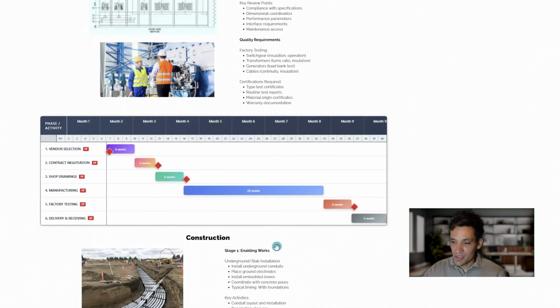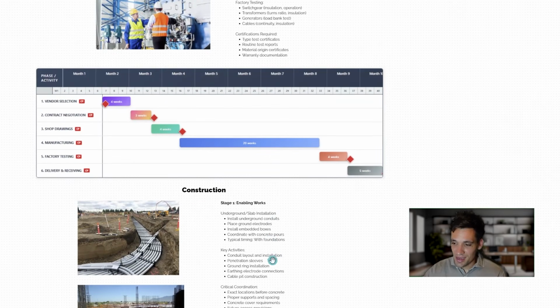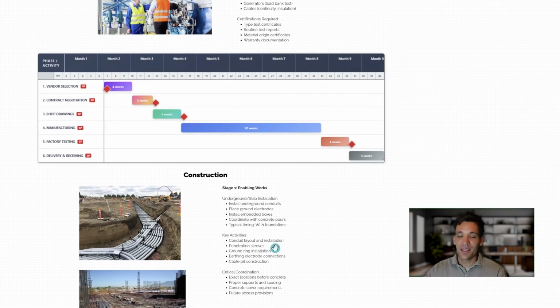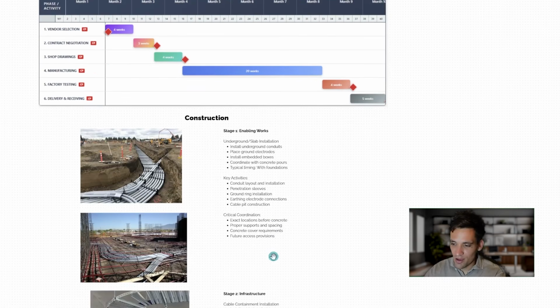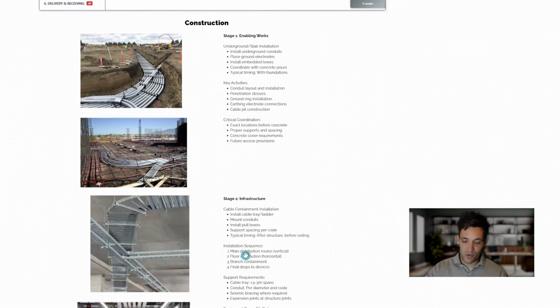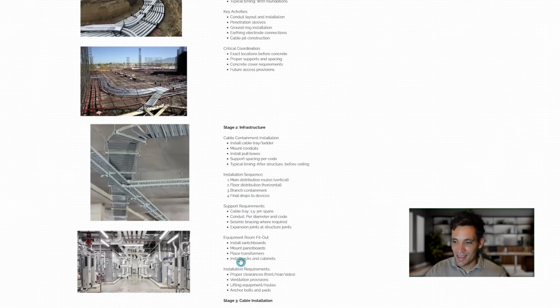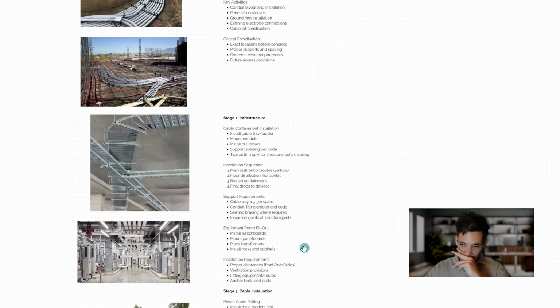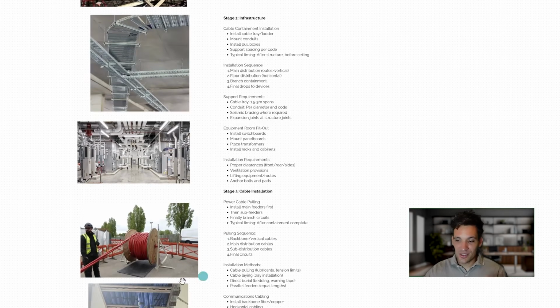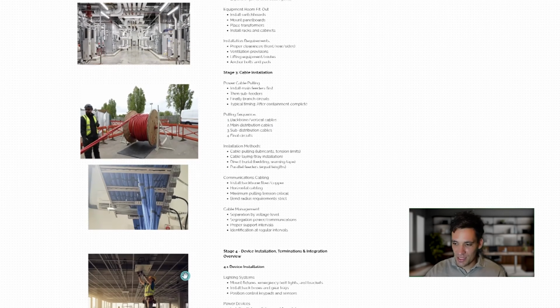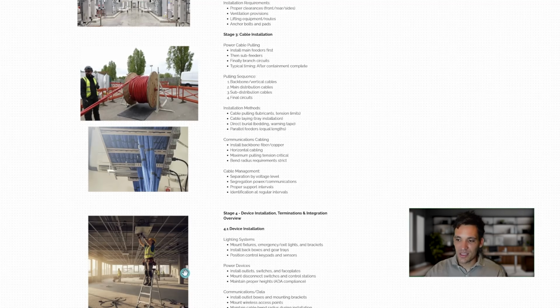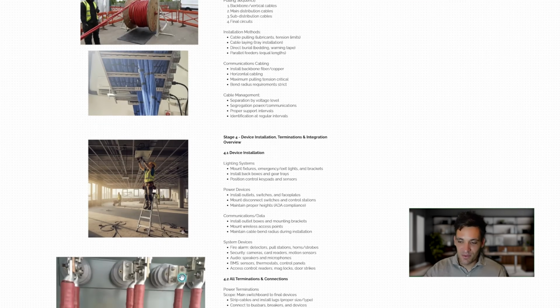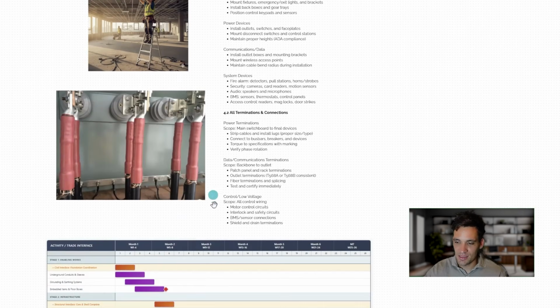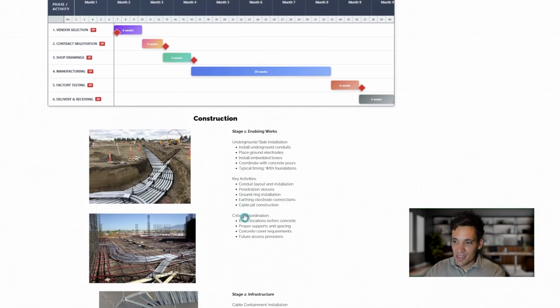Once we've got all the gear on site, what's next? Well, it's time to start putting it all together, and that's where we enter the construction phase. I've broken the construction phase up into a couple of separate steps: enabling work, so all the in-ground services and preparation; the actual infrastructure, so putting in the cable tray and installing switchboards; the cable installation, so the cable pulling and the cable terminations; and finally the installation, termination, and final configuration of all the equipment.